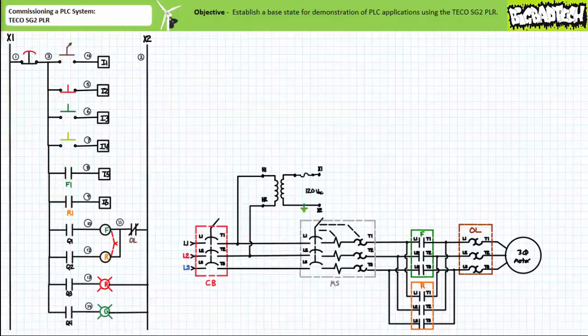Let's now examine the output configuration. Electromechanical relay output Q1 energizes or de-energizes the F contactor coil hardwired with the normally closed overload contact. Electromechanical relay output Q2 energizes or de-energizes the R contactor coil also hardwired with the same normally closed overload contact. This hardwired connection between the F and R contactor coils and the normally closed overload allows the overload to have the last say as to whether the motor is energized or not, and never surrenders complete authority to the PLC.